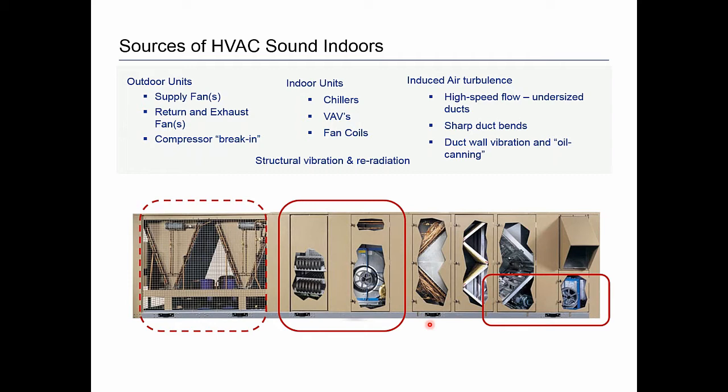With indoor units, noise can come from chillers, variable air volume boxes, and fan coils. Noise can be induced by air turbulence, which is particularly a problem with high-speed flow and undersized ducts. Very sharp duct bends also generate a great deal of turbulence that can turn into noise. If the turbulence is low enough in frequency or pulsation rate, it can induce actual duct wall vibration or oil canning. Finally, there are many paths by which structures can vibrate and then re-radiate sound indoors.